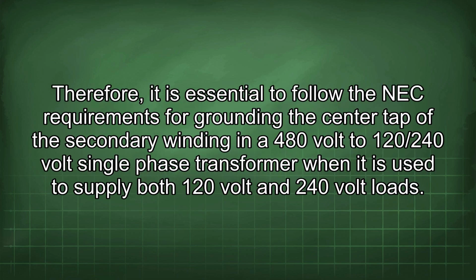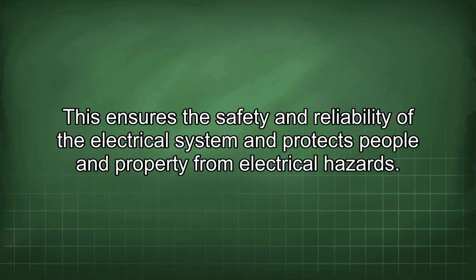Therefore, it is essential to follow the NEC requirements for grounding the center tap of the secondary winding in a 480 volt to 120/240 volt single-phase transformer when it is used to supply both 120 volt and 240 volt loads. This ensures the safety and reliability of the electrical system and protects people and property from electrical hazards.